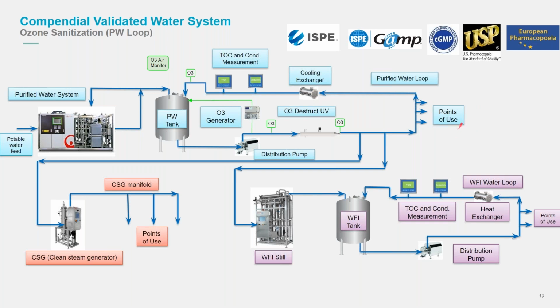And if we're talking about USP quality purified water, we're looking at 3 parameters: conductivity, TOC, and microbial. Conductivity less than 1.3 microsiemens at 25 degrees. In terms of bacteria, we're looking at less than 100 CFU per mil. And in terms of TOC, total organic carbon, we're looking at less than 500 parts per billion at the point of use. And in order to achieve that and to protect the product, as I say, the product has a value, we tend to over purify at the front end here. That allows for any degradation within the storage and distribution system or any pickup, to make sure that you're well within those USP standards or European standards, etc., at the point of use here.